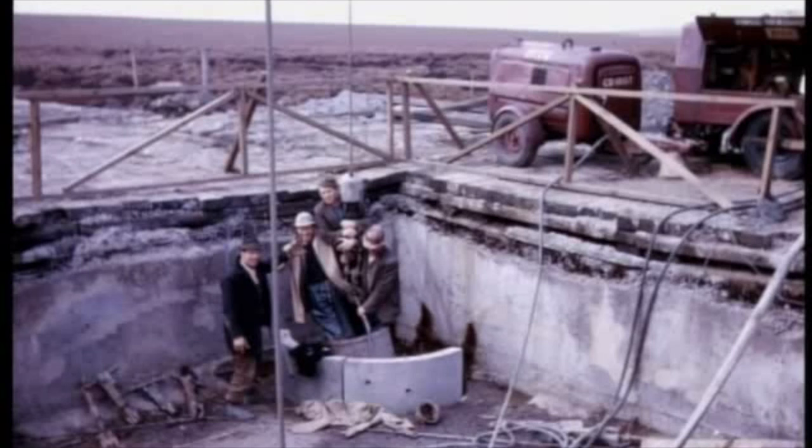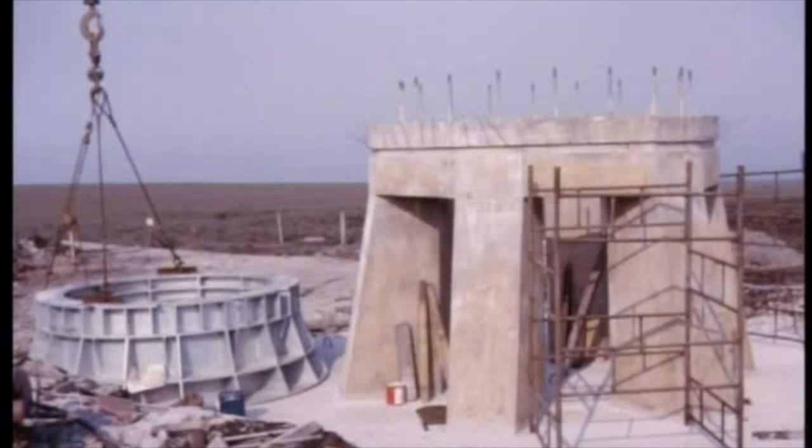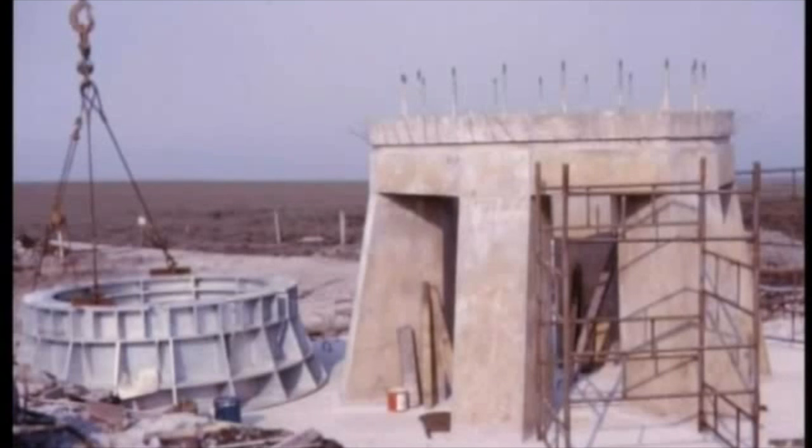They constructed a platform like a big kitchen table. The tabletop is 30 foot square and 8 feet thick, with its four legs 9 feet in diameter, standing on the bedrock 55 feet below, all made of high-grade reinforced concrete. The picture shows the excavation for the tabletop and the excavation of one of the leg holes in progress. A massive cage of reinforcing steel was installed in the leg holes and the platform space, followed by a few days with a fleet of concrete lorries coming up the hill pouring concrete non-stop. A few weeks more and we have a nice flat platform carrying the concrete mass plinth structure.